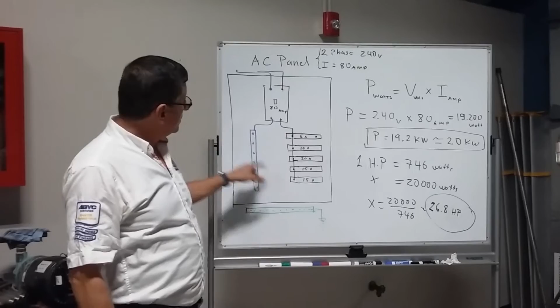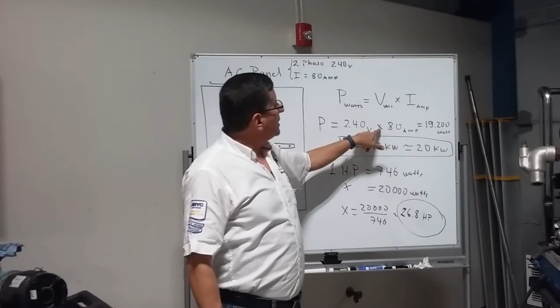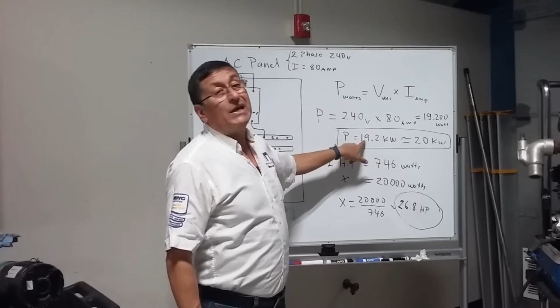Okay, in this particular case, the capacity of the main breaker in this boat is 80 amps. And this boat is double phase, 240 volts. It's simple. I am going to use Ohm's law. If you remember, Ohm's law states that the power in watts should be equal to the voltage in volts times the intensity in amps. In other words, in this particular example, the power should be 240 times 80, because this is the capacity of the breaker. 240 times 80 is 19,200. Okay, this is 19.2 kilowatts.